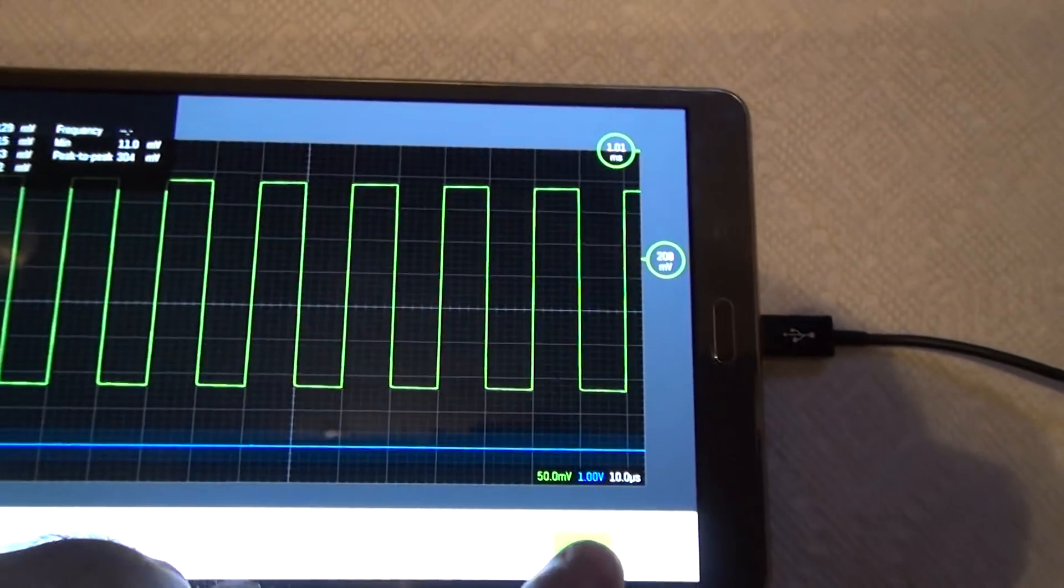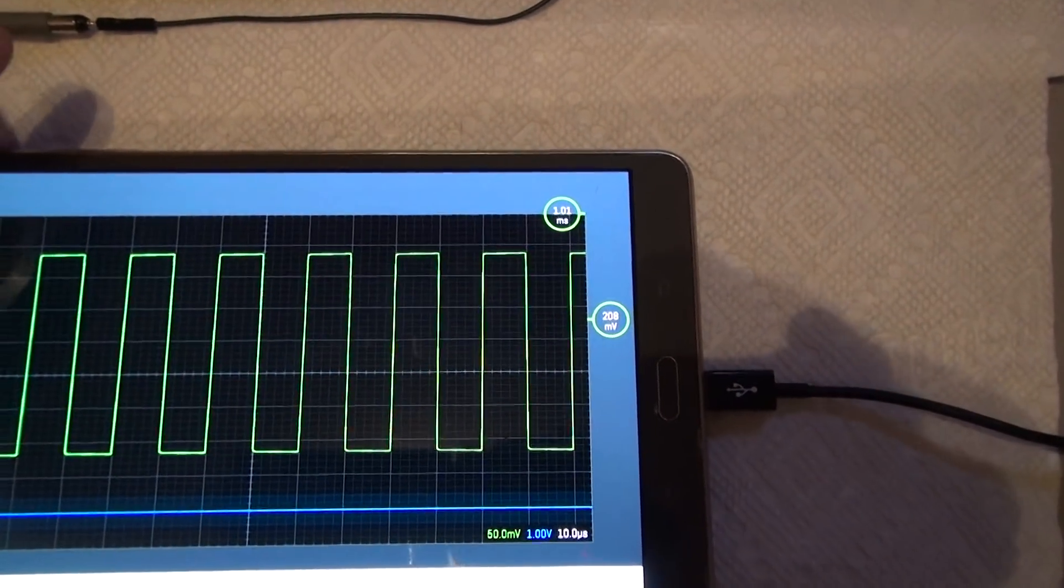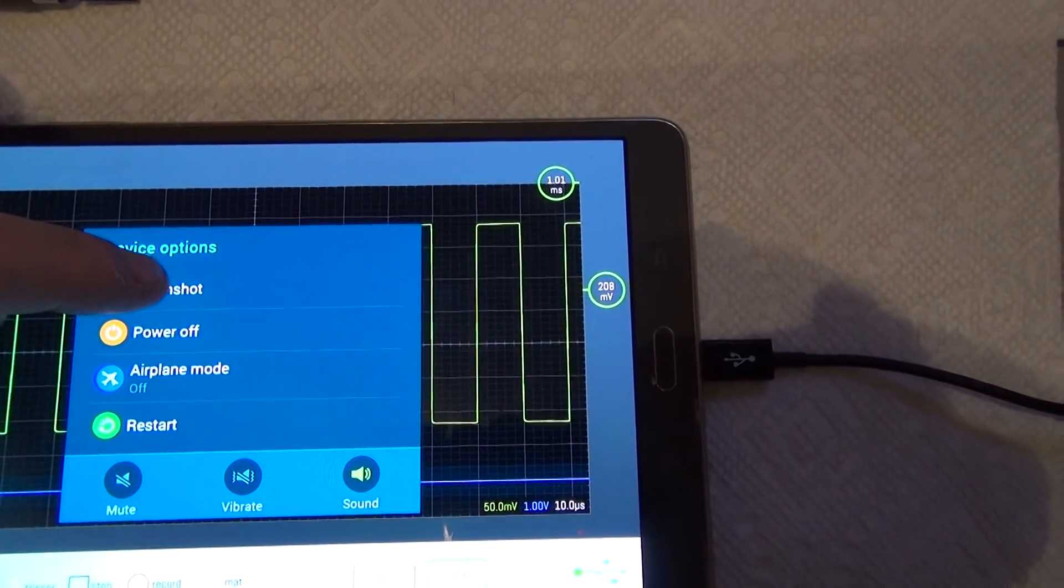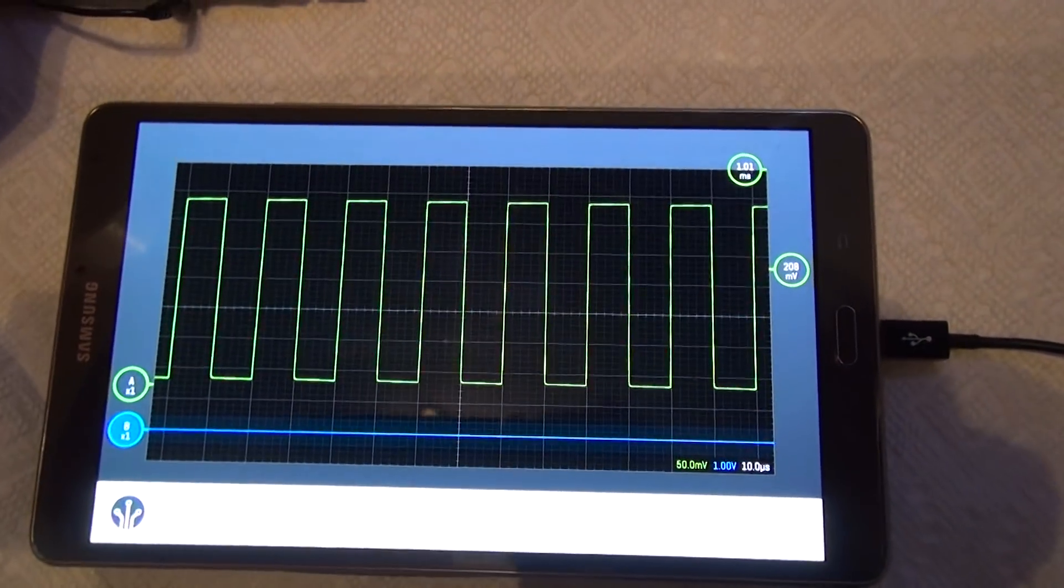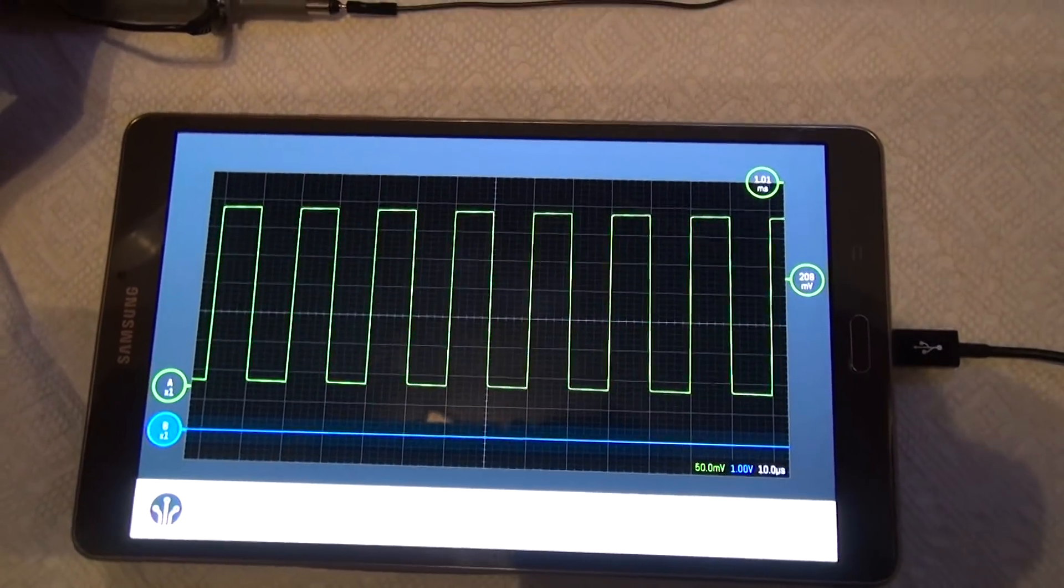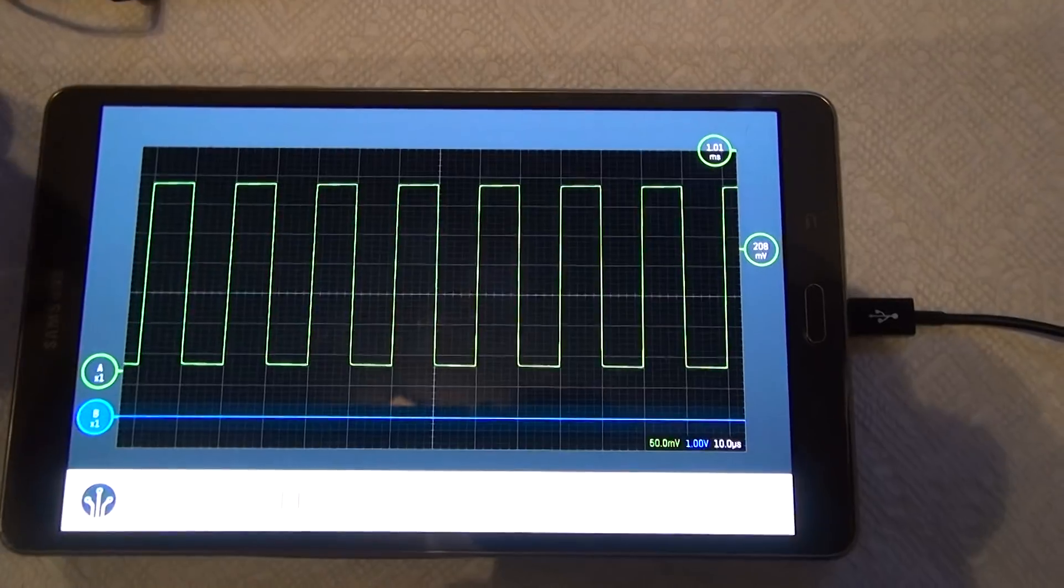If I don't want that on the screen I can get rid of it. On my Galaxy Tab I got it set up so I can do a screenshot just by pushing the power button and clicking on screenshots. So right there, that's stored this waveform on my SD card so I can take multiple waveforms and save them. I do this on the machines I work on. I save all the waveforms so I've got reference waveforms for the machines. When I have problems I can refer to them.